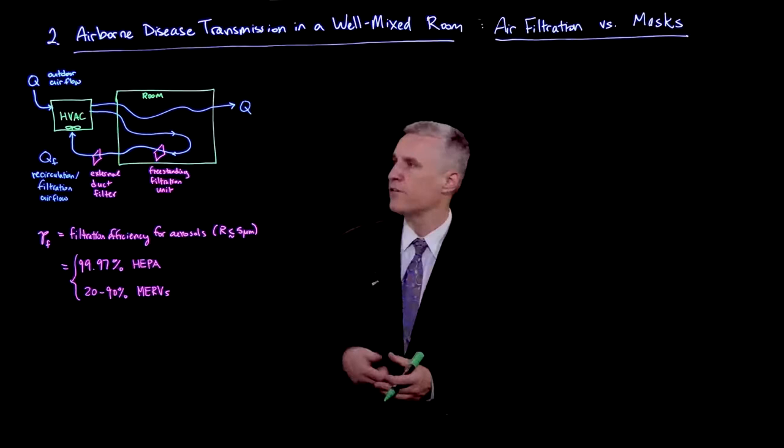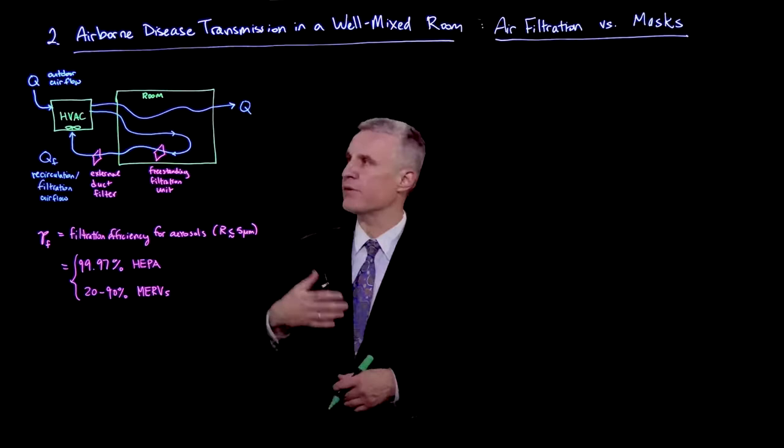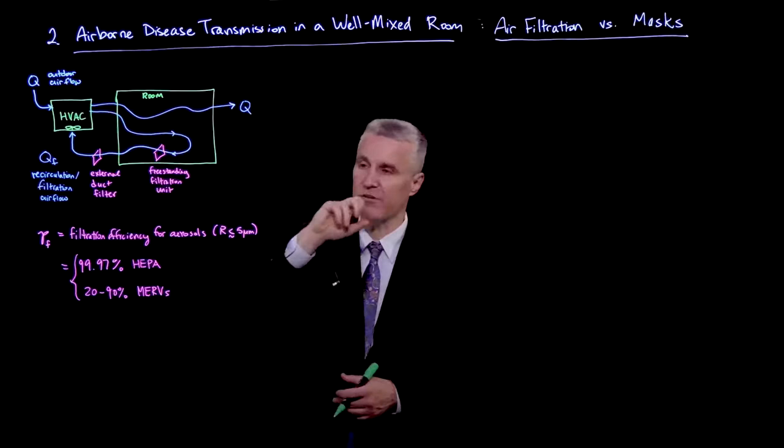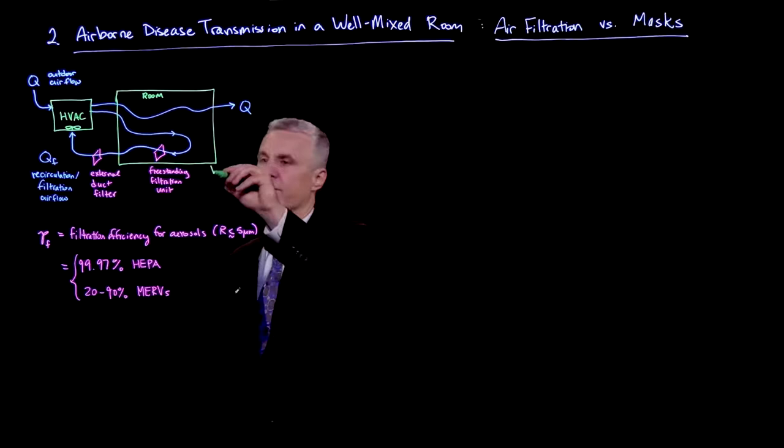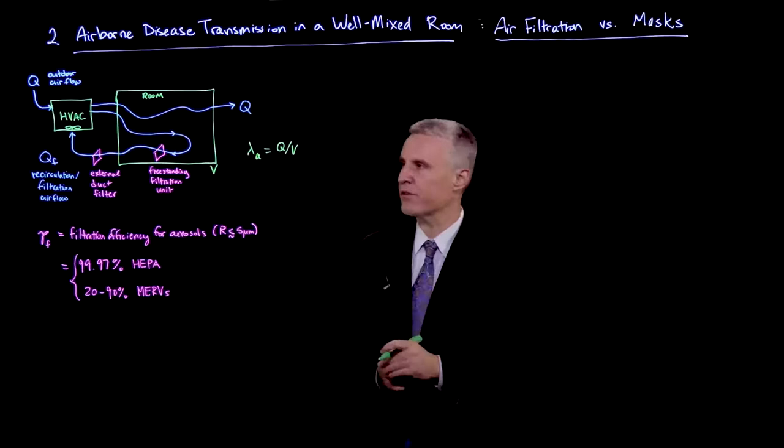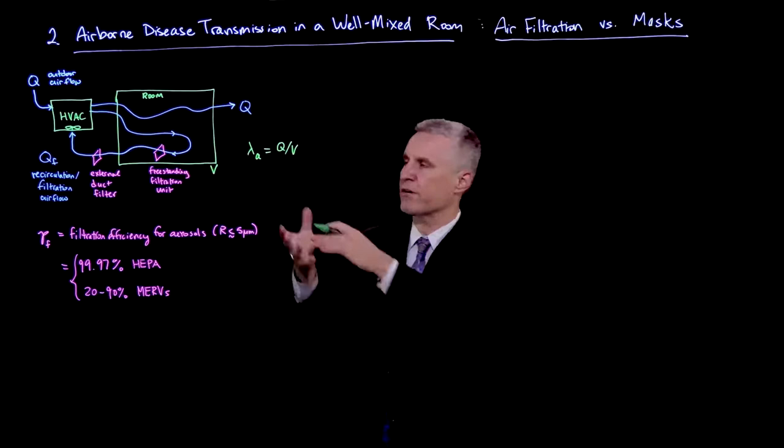So here's a schematic sketch of the air flows. We still have this Q, which is the outdoor air flow coming in from outdoors and leaving. The air change rate is based on that Q. If there's a volume V of the room, then the air change rate lambda_A was Q over V. That's units of inverse time, the residence time for the outdoor air and the changing of the air.